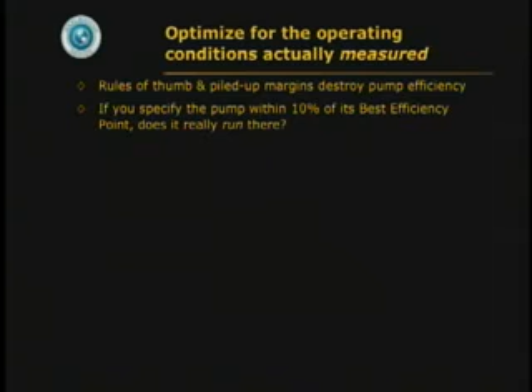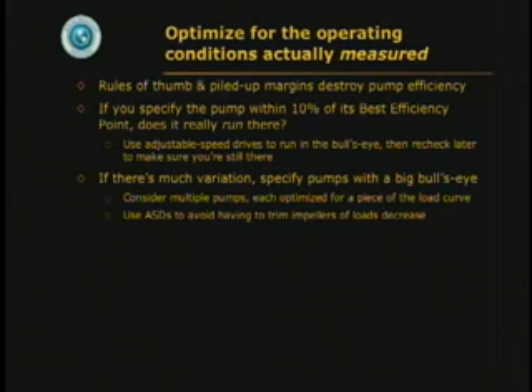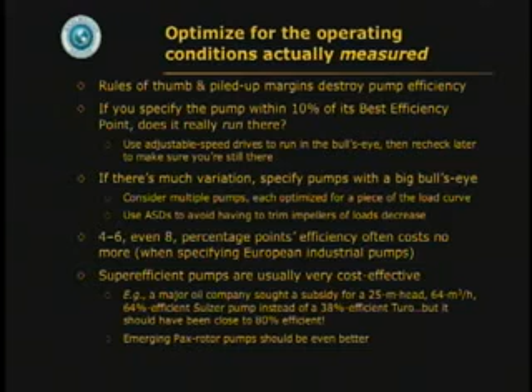Of course, all pumps, whatever size, should be optimized for the actual measured operating conditions, because it's rules of thumb and piled up margin upon margin that destroy pump efficiency, not just choosing bad pumps. Do you check whether the pump actually runs in the conditions you think? Do you use adjustable speed drives to make it run in its efficiency bullseye and then keep checking to make sure it's still there? And of course, if your process keeps varying the load, specify pumps with a big bullseye, so even if you're a little off on the operating conditions, it'll still work well. Maybe have multiple pumps, big and medium and small, each optimized for its piece of the load curve instead of trying to do it all with one pump. And use adjustable speed drives for flexibility. Buy great pumps, they're very cost effective. And of course, then we have those biomimetic rotors coming at us, which are even better.